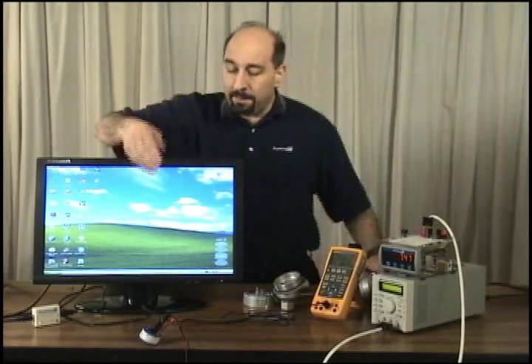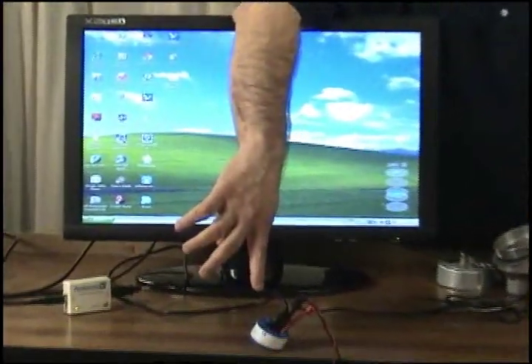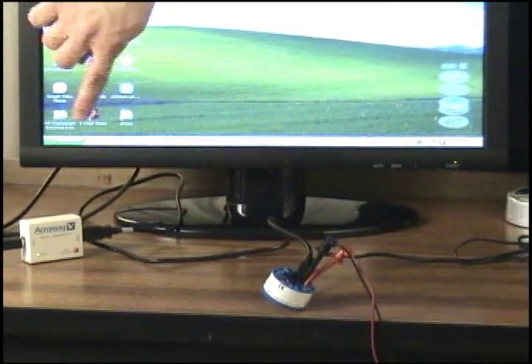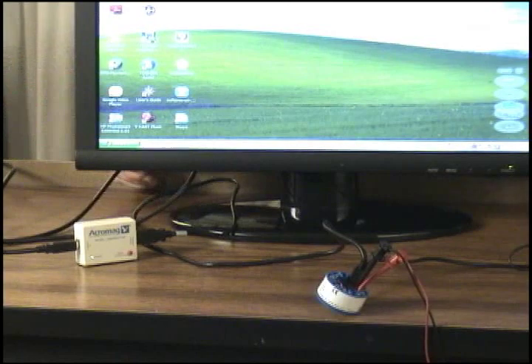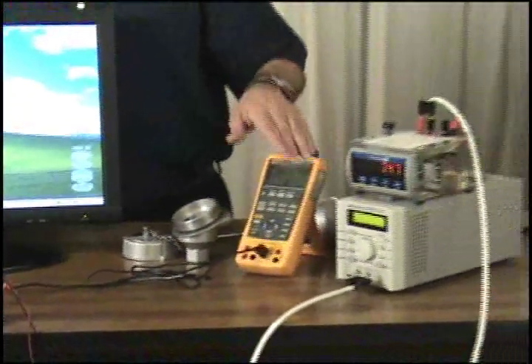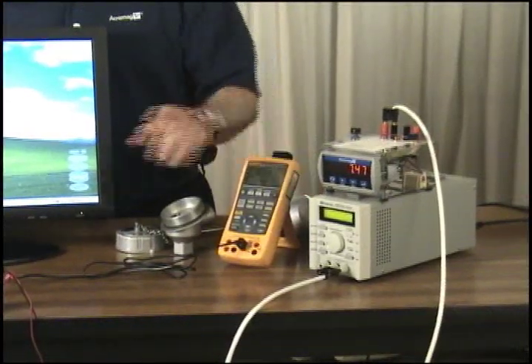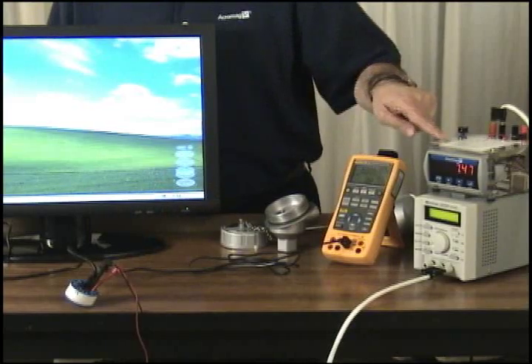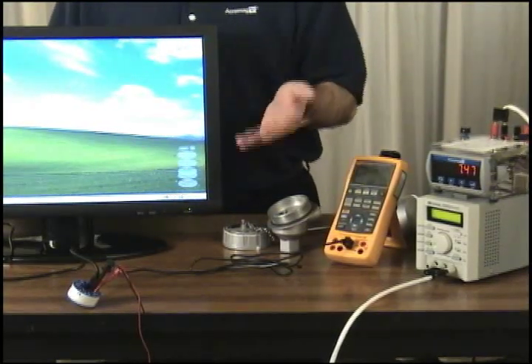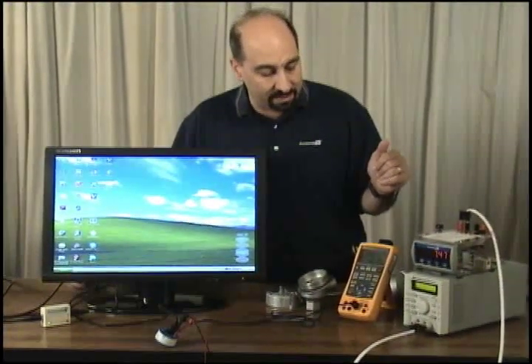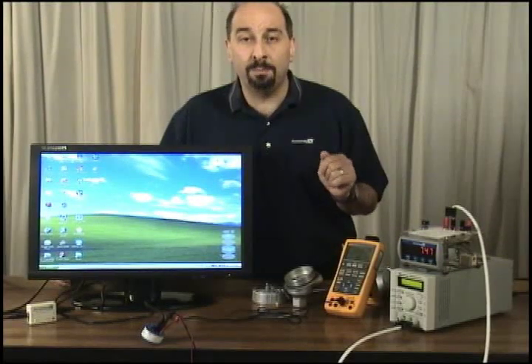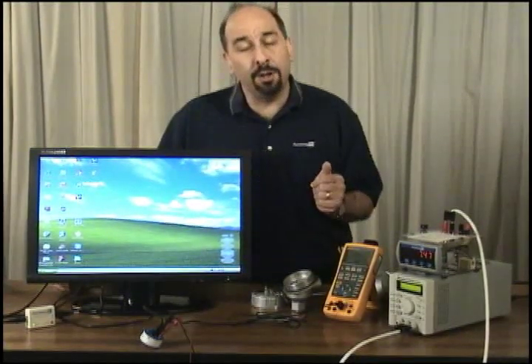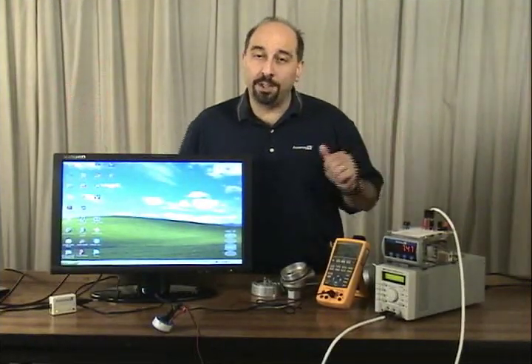Okay, today my setup for you is an ST132 temperature transmitter product. I'm USB connected to it through Acromag's USB isolator to my PC. I've got a type J thermocouple pre-wired to the input from my Fluke source and I have a 24 volt power supply powering the output loop bringing back 4 to 20 milliamps into my Acromag meter. Right now the unit is default type J thermocouple over the whole range, minus 210 to 760 C. I'm injecting zero degrees C and I'm reading what I would expect 7.47 milliamps out. Basically this is how you're going to receive the product out of the box is type J thermocouple over the whole range as default.